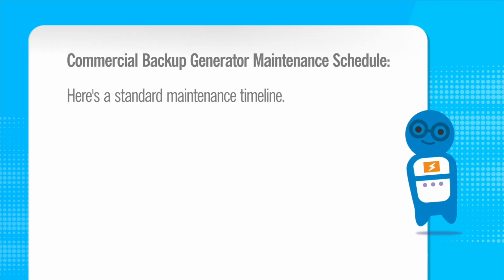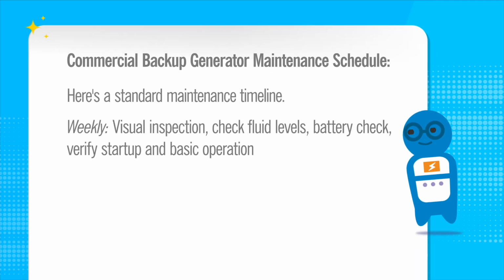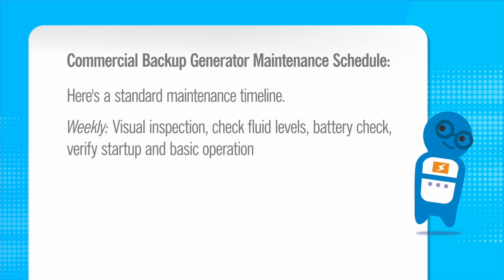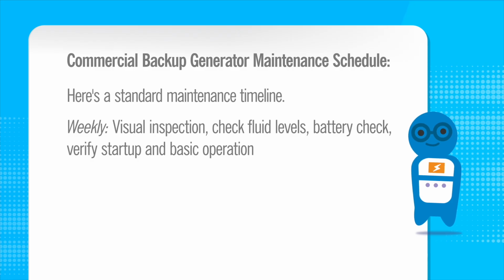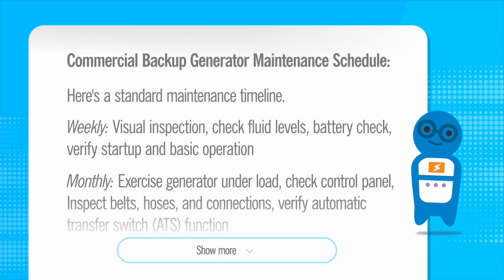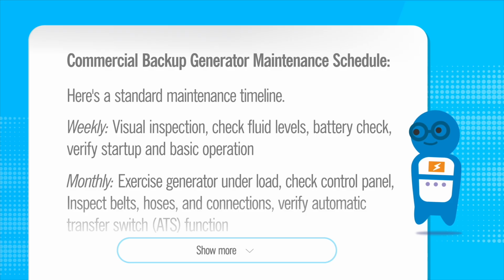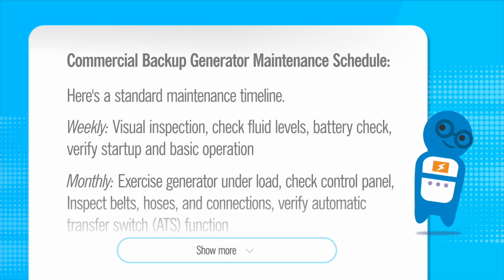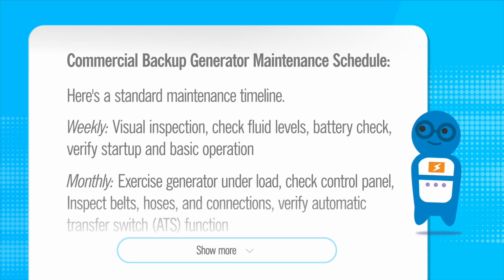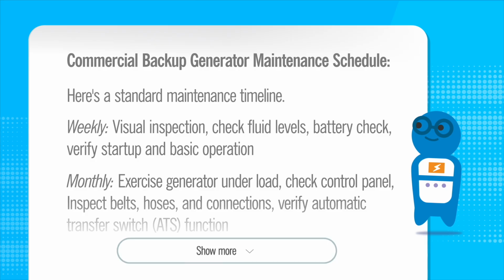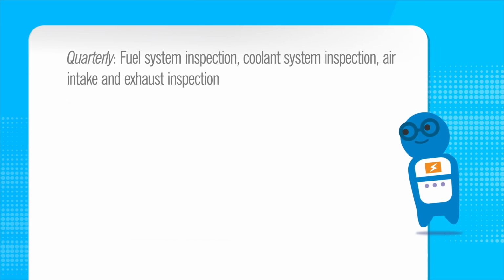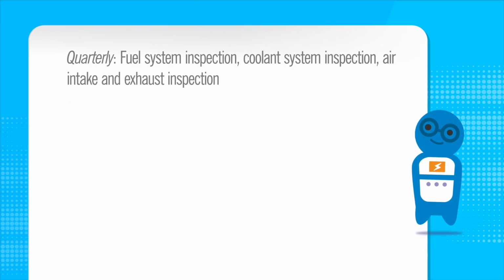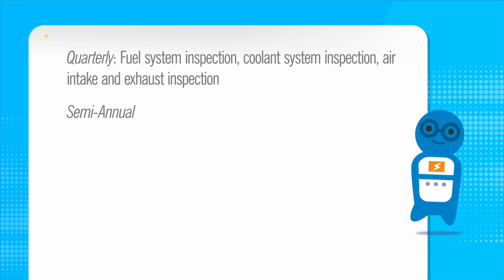Here's a standard maintenance timeline. Weekly: visual inspection, check fluid levels, battery check, verify startup and basic operation. Monthly: exercise generator under load, check control panel, inspect belts, hoses, and connections, verify automatic transfer switch function. Quarterly: fuel systems inspection, coolant system inspection, air intake and exhaust inspection.